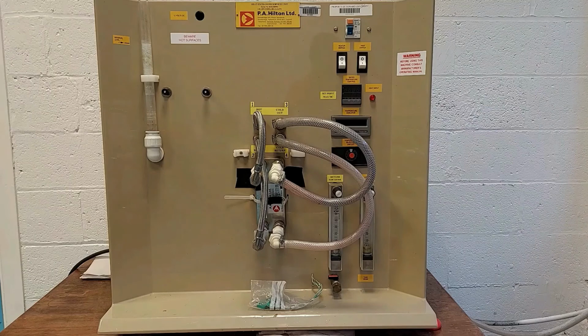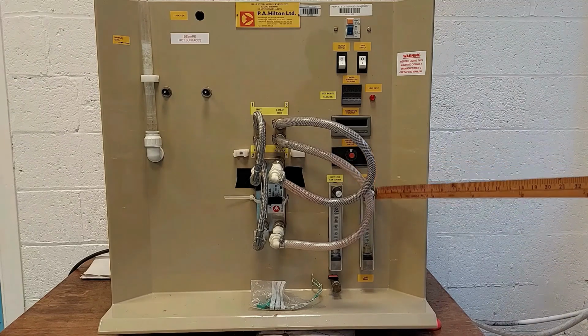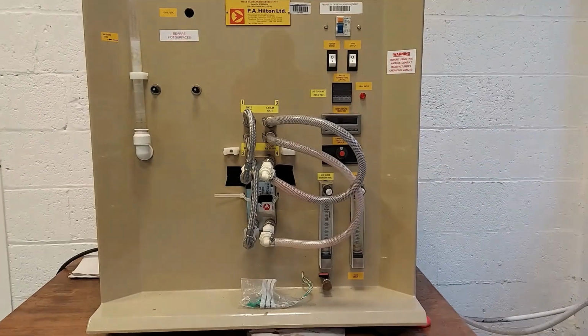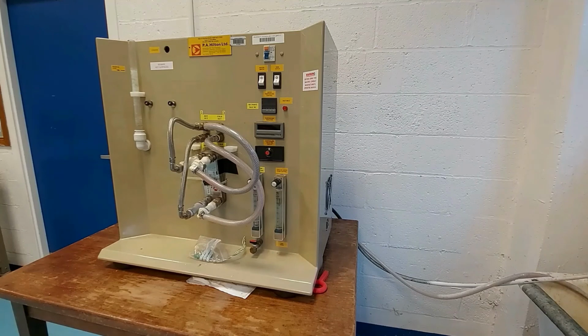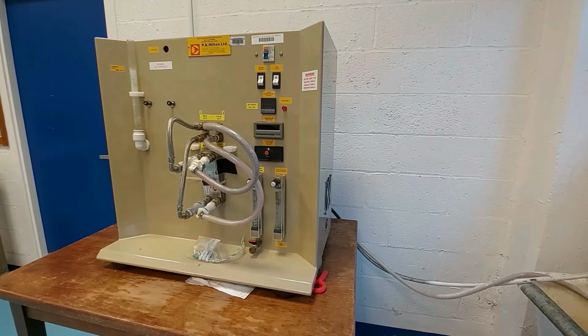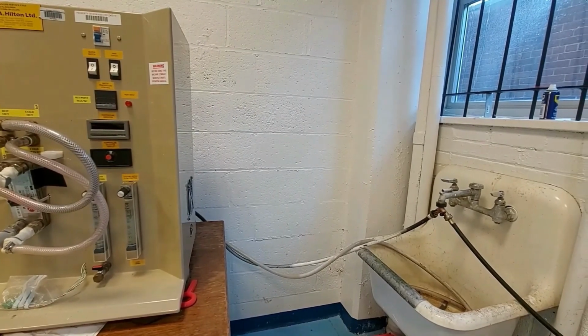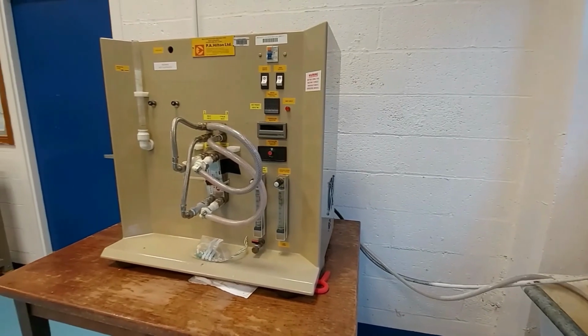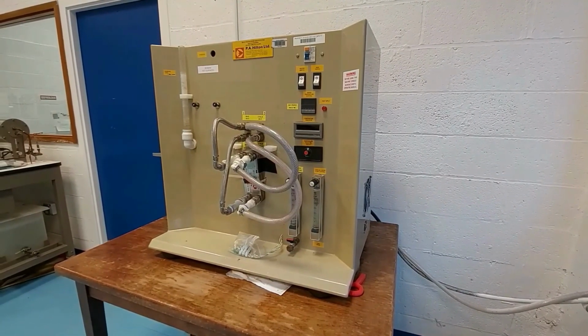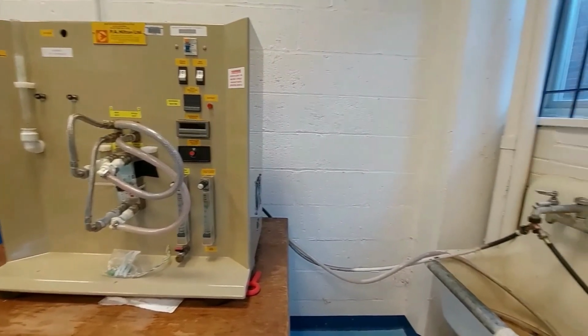Now, let's move on to the other components of the equipment. Next, we will be looking at the water supply, both hot and cold. The hot water supply comes from a heater reservoir inside the unit. It is maintained and filled by adding water at this inlet. This hot water then cycles through the system continuously. Next, the cold water supply comes from a pipe tapping, so a continuous flow of room temperature water enters the plate heat exchanger, and the heated water exits into the drain.